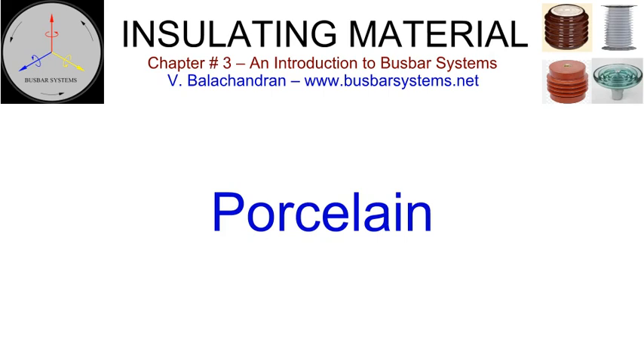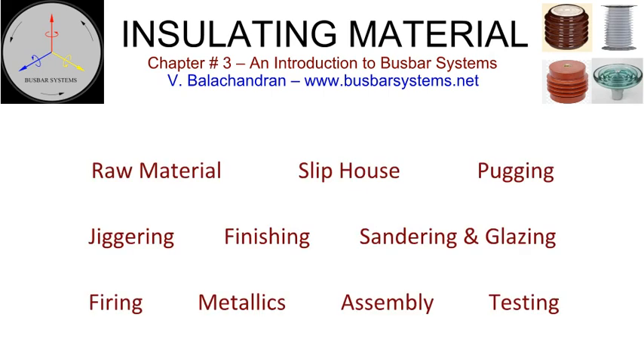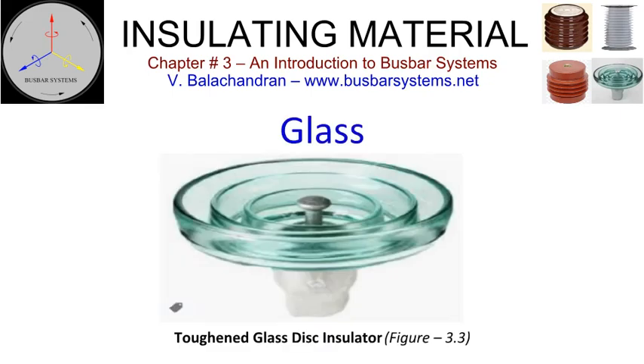Porcelain insulators have excellent resistance to water absorption. The porcelain manufacturing process, in brief, comprises raw material, slip house, pugging, jigging, finishing, sandering and glazing, firing, metallics, assembly, testing. Glass. Disc insulators made of glass have been used in transmission lines for the past few decades. These have not been installed as bus support insulators either in an open bus or metal enclosed bus. The reason for it becomes evident when one understands the manufacturing process.